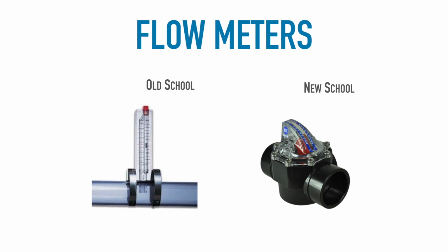Another thing that you'll see is sometimes you'll shut your system off and miraculously your flow meter is still reading 140 gallons per minute or whatever it may be. The reason this happens is because you get a bunch of calcium buildup inside of that old school flow meter and it sticks that float, or that bullet, inside there in one spot. So then you've got to uninstall it from the line, pour something slightly or mildly acidic like vinegar down inside there, shake it around, clean it out, reinstall it, and start the system up.